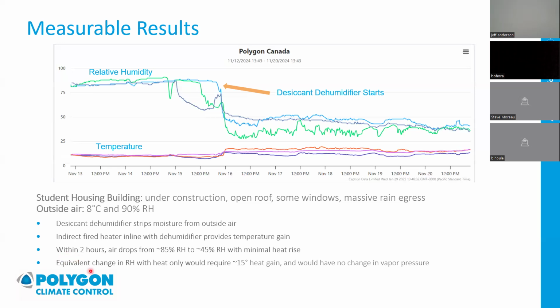If you were trying to achieve this same RH change using heat alone, you'd actually have to get about a 15-degree heat gain as opposed to this desiccant drop we get here, and you would have no change in vapor pressure if you did that. You'd have to crank up the heat like crazy, burn a lot of gas, use a lot of electricity, but you'd still potentially have the exact same vapor pressure between your air and the materials. So there's no guarantee you would dry, even if you managed to achieve this kind of drop in relative humidity by using heat. That's interesting.